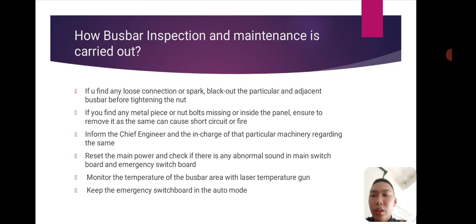Next, reset the main power and check if there is any abnormal sound in the main switchboard and emergency switchboard. Monitor the temperature of the bus bar area with a laser temperature gun. Keep the emergency switchboards in auto mode.